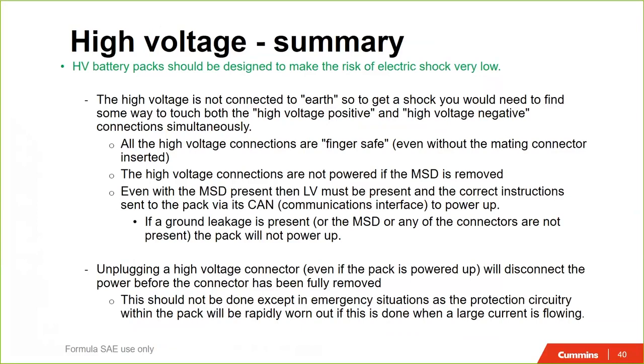High voltage connections are not present if you have an MSD and it's removed. Even if you have the MSD present and your systems are the same from what I've read of the rules, low voltage must be present and the correct instructions sent to the pack via CAN to power it up. There also has to be a demand from the system as well, again, before the battery will generally deliver voltage current.